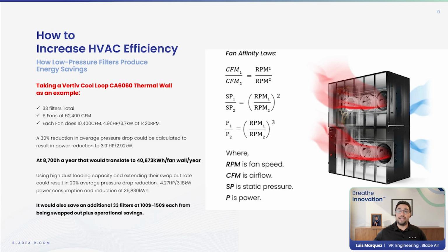So our initial fan consumption of 4.96 horsepower goes down to 3.91 horsepower or 2.92 kilowatts. If we leave some downtime for filter swap outs and maintenance, we can say at 8,700 hours a year, that would equate to almost 41,000 kilowatt hours a year for each fan wall. So many data centers use many of these fan walls, so it can really add up to increased efficiency and a lot of money savings.